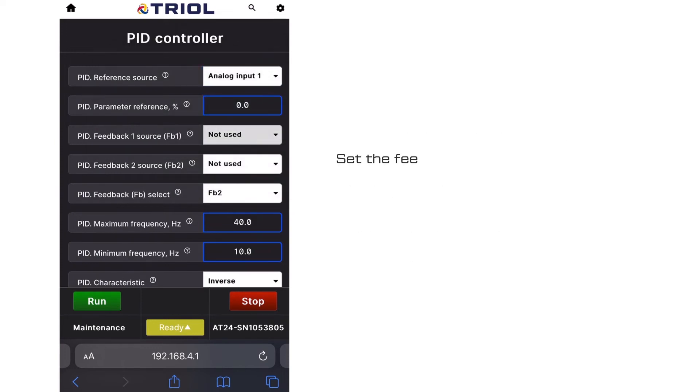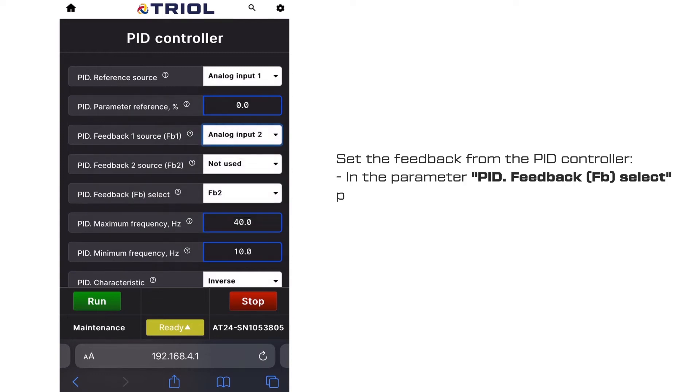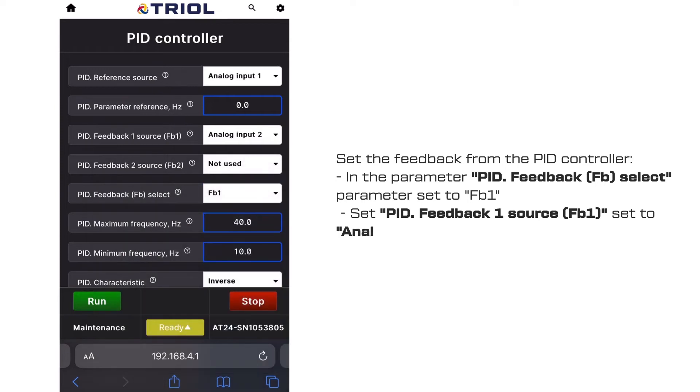Set the feedback from the PID controller. Set the PID feedback (FB), select parameter to FB1. Set the PID feedback 1 source (FB1) to analog input 2.